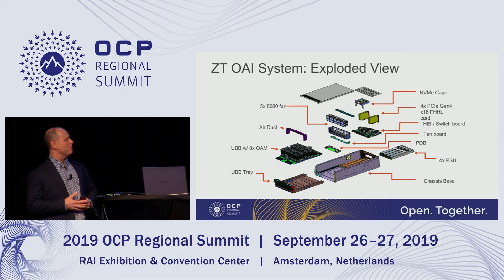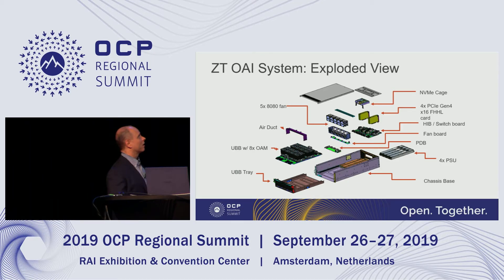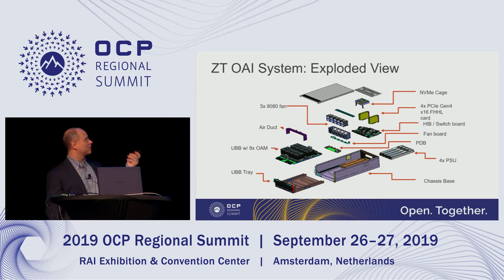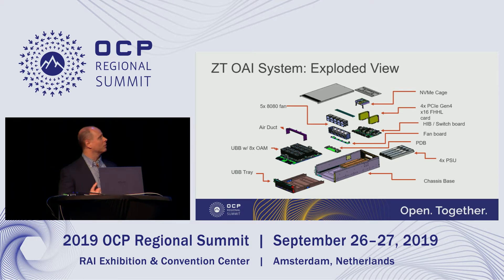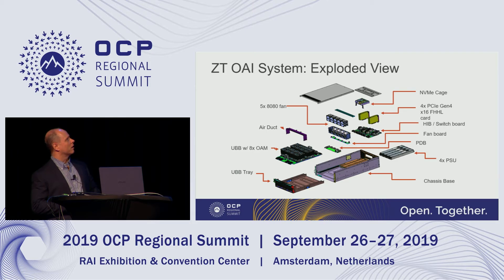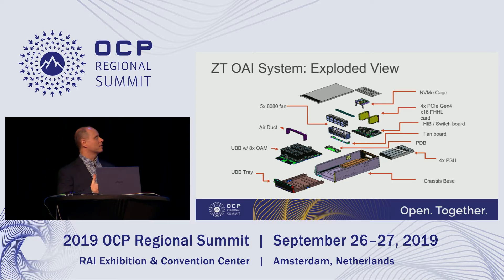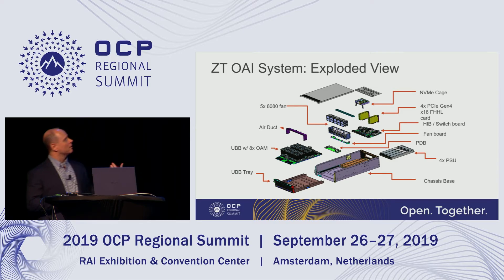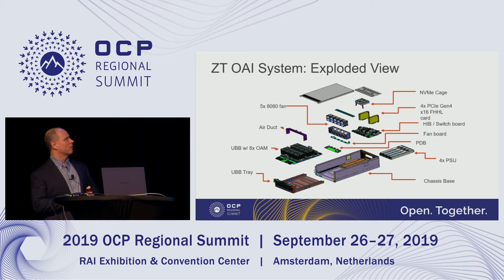This is an exploded view showing all elements of the system. We have the UBB with the eight accelerator modules — all of those fit on a UBB tray, and the UBB tray slides out from the chassis base. The host interface board plugs in on the same level as the UBB board. We have a fan board that supports the fans with fan control, and then the four 3-kilowatt power supplies that fit in the bottom 1U of the chassis.